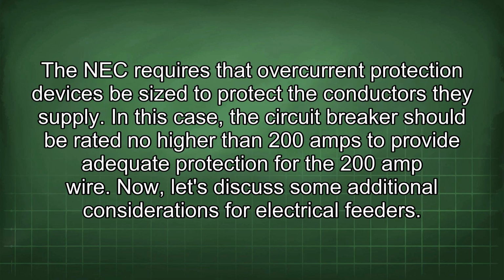The NEC requires that overcurrent protection devices be sized to protect the conductors they supply. In this case, the circuit breaker should be rated no higher than 200 amps to provide adequate protection for the 200 amp wire. Now, let's discuss some additional considerations for electrical feeders.